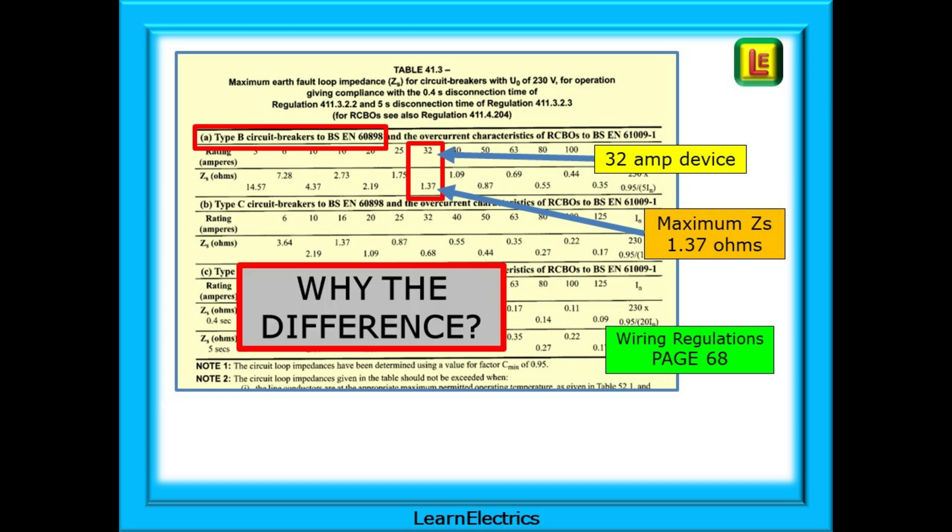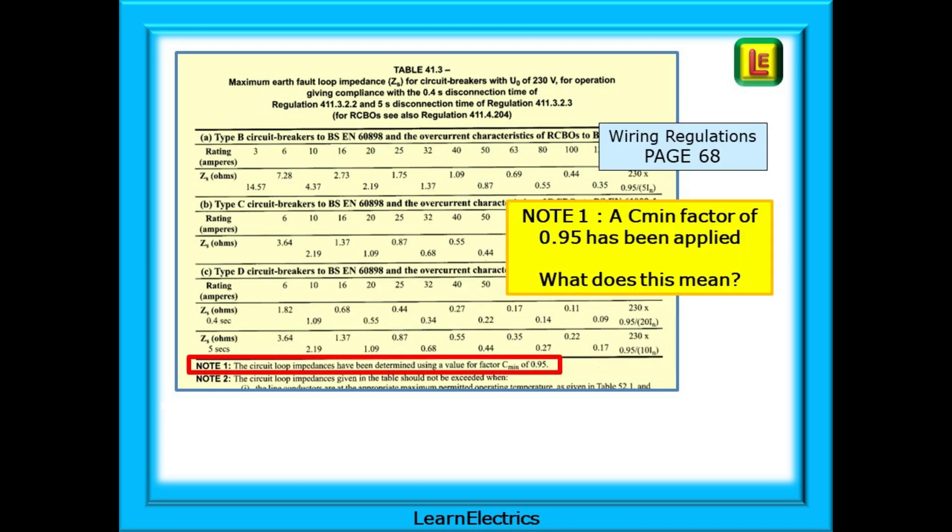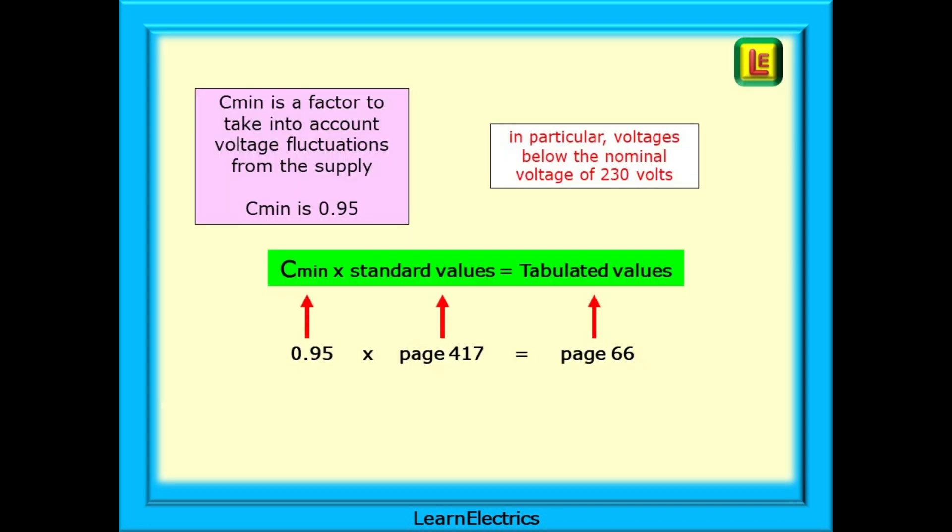So already we found a difference between the tabulated data and the standard or raw data that we started with. Why the difference? Look at just below table 41.3 on page 68 at note number 1 highlighted here in red. It tells us that a Cmin factor of 0.95 has been applied to determine the loop impedance values or ZS. What does this mean? Cmin is a factor to take into account voltage fluctuations from the supply. And it tells us that Cmin is 0.95.